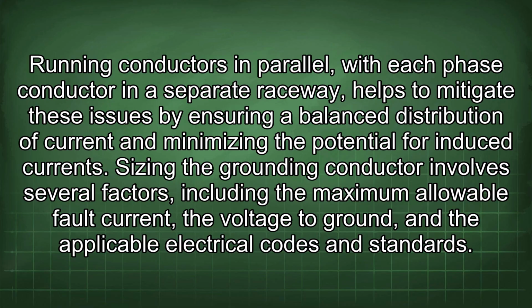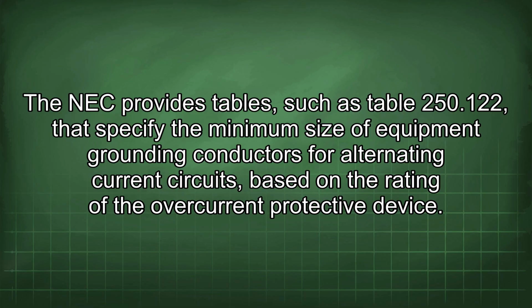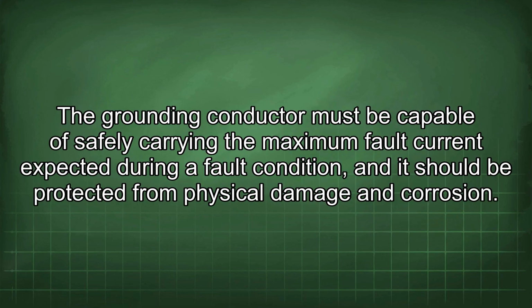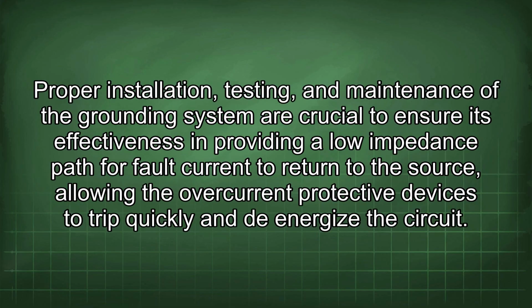Sizing the grounding conductor involves several factors, including the maximum allowable fault current, the voltage to ground, and the applicable electrical codes and standards. The NEC provides tables such as Table 250.122 that specify the minimum size of equipment grounding conductors for alternating current circuits based on the rating of the overcurrent protective device. The grounding conductor must be capable of safely carrying the maximum fault current expected during a fault condition, and it should be protected from physical damage and corrosion. Proper installation, testing, and maintenance of the grounding system are crucial to ensure its effectiveness in providing a low-impedance path for fault current to return to the source, allowing the overcurrent protective devices to trip quickly and de-energize the circuit.